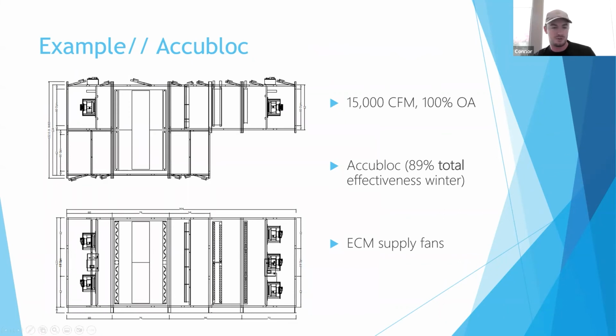It's set up similar to our stacked plate heat exchangers. This specific example is 15,000 CFM, 100% OA application. And this gets you almost 90% total effectiveness in the winter. An advantage here is that you don't need frost protection because of the modulating airflow. So you can size your heating load for your worst case, which would be the AccuBlock 90% effectiveness.